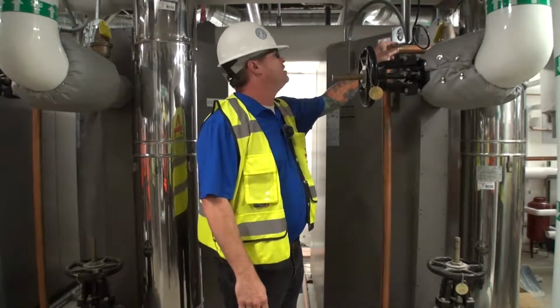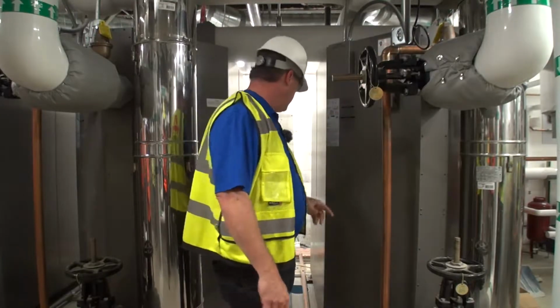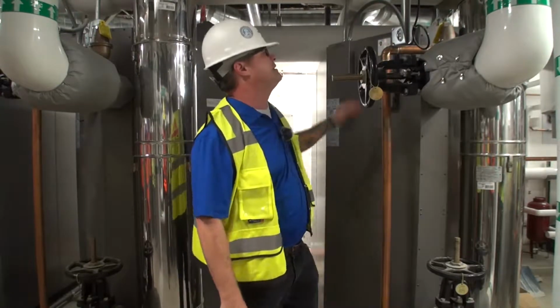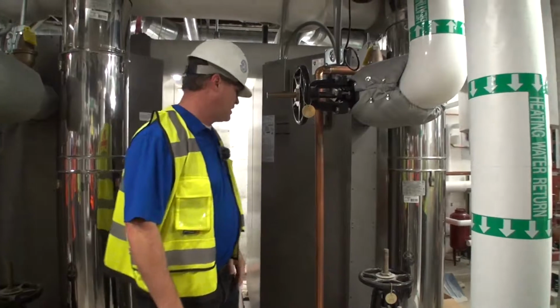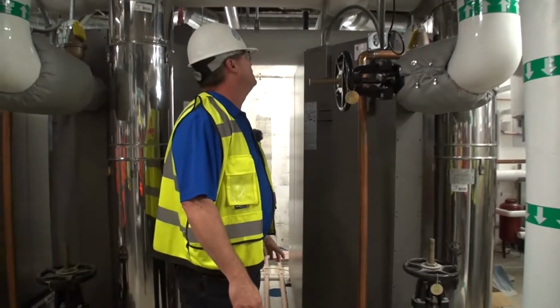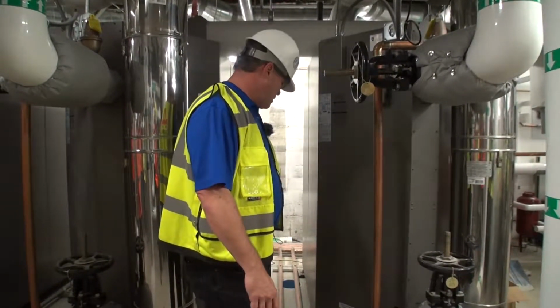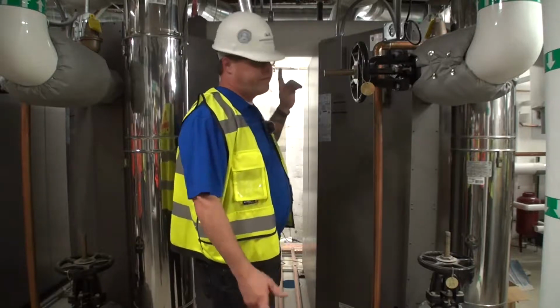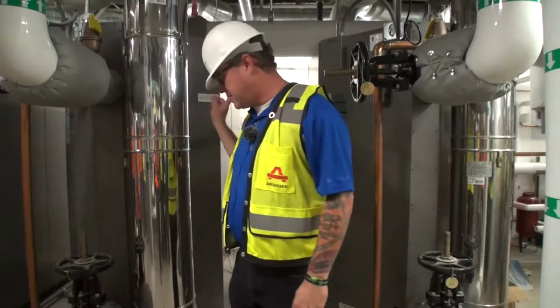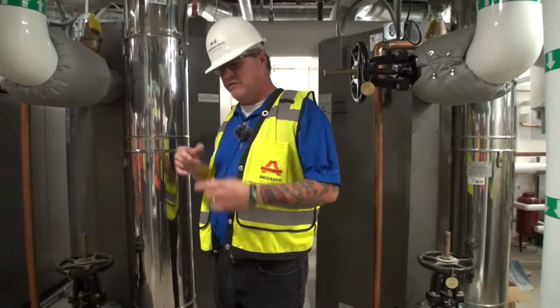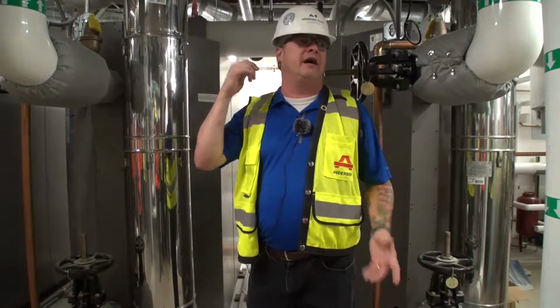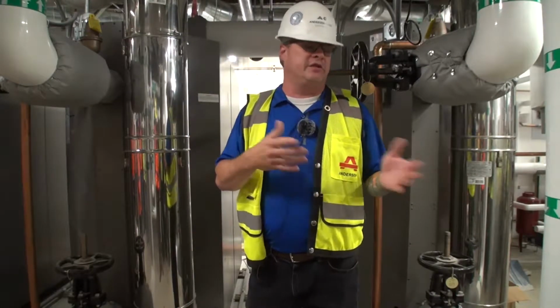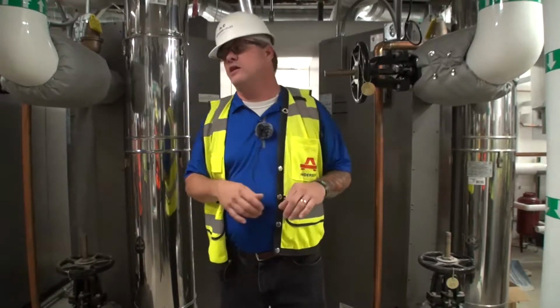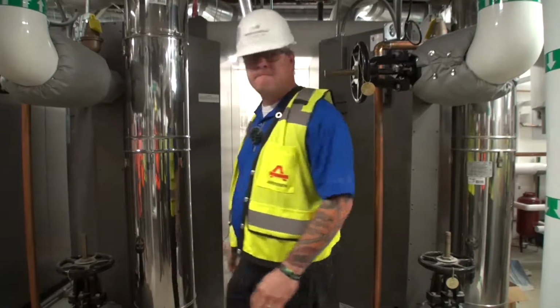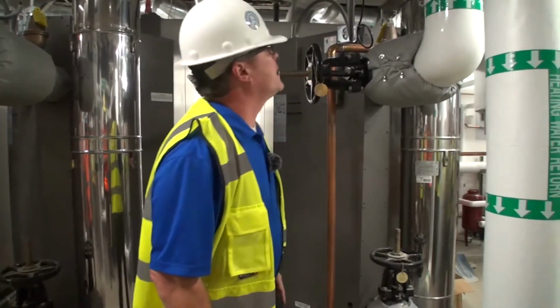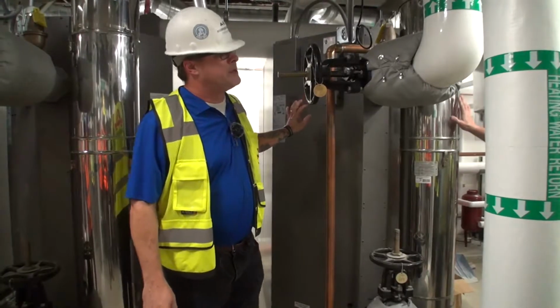Also, we look at the relief valves, in the sense of leaking or anything like that. They could be hung up, stuck, or, like I said, need to be replaced. Other than that, on the front side we can go to the front side, and I'll let Sheldon take over. There's a filter on here that we need to look at about every 6 months to a year, just as well as the neutralizer.